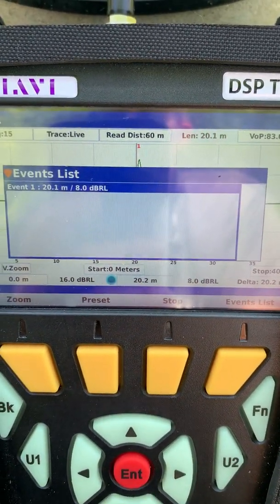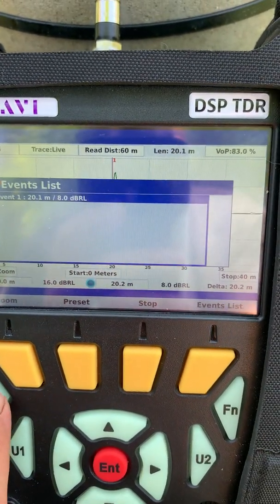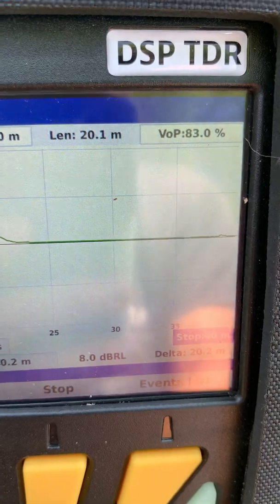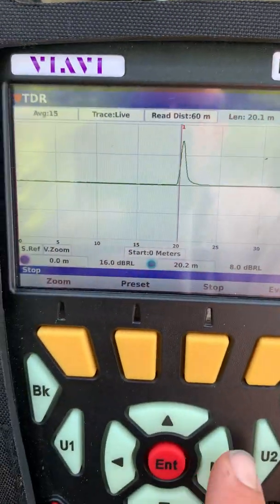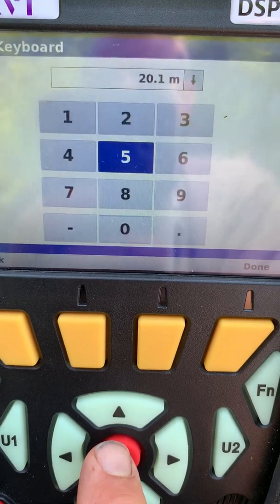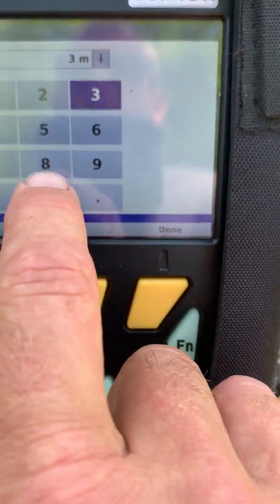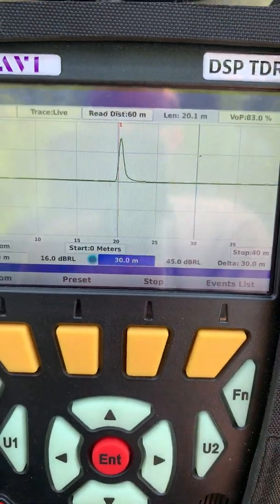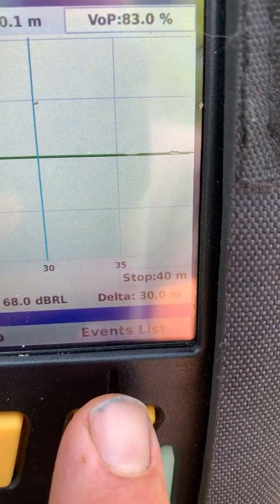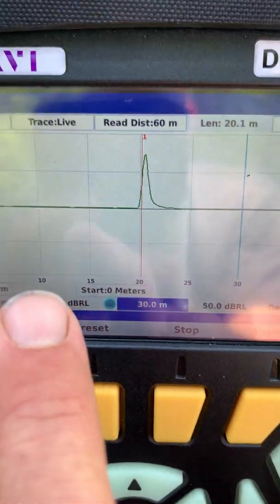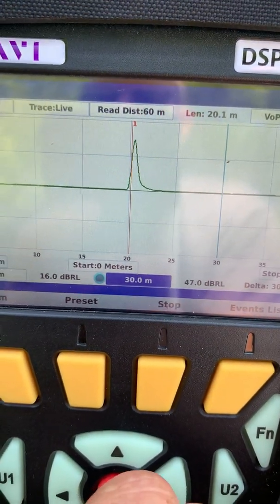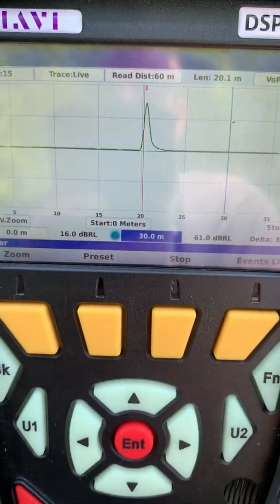With the profile all set up, you can see it's just a couple of button pushes and you're right where you need to be. You can see the fault, and my marker has already been set to it. The quickest way is to go to the Events List, but if you want to change the marker you can arrow through the selection, hit enter, and type in a value — say 30 meters — and hit done. The marker moves over accordingly, and the distance between the two markers is shown as well. Events are numbered, so if you have multiple faults on the cable you'll see event one, two, three, and so on.